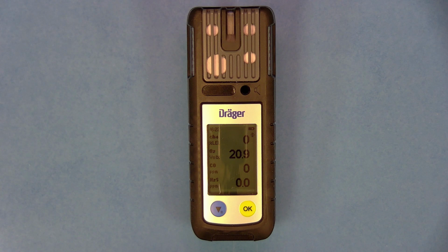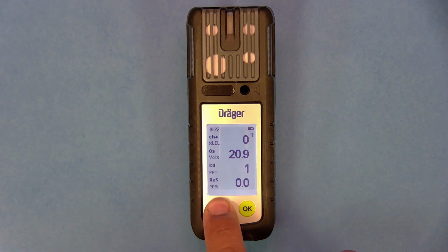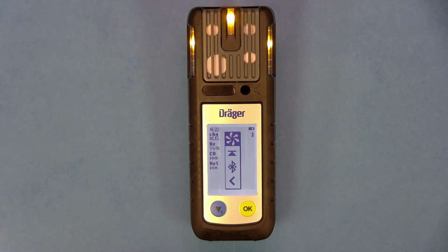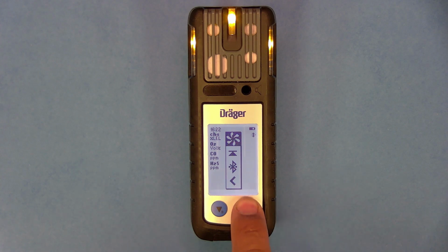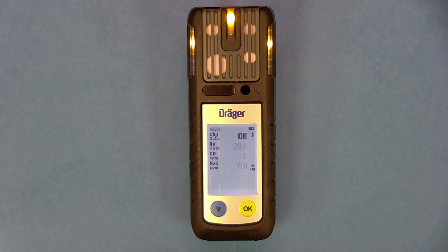Periodically, you might want to zero your gas detector. This process is also frequently called fresh air calibration because you are calibrating your oxygen sensor to ambient 20.9% oxygen. To enter the fresh air cal or to zero your monitor, you'll press the blue button 3 times quickly to enter the screen showing the quick menu, and you're going to be looking for an icon that looks like a fan right there on the top. You're going to push the OK button and the zero process will begin.